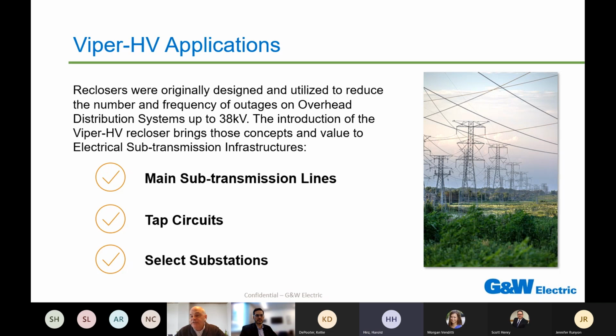On that main line is a series of taps. Those taps could be for industrial customers or interconnects, but this particular product is really conducive for those taps, where now you have complete overcurrent protection. Only that tap will be de-energized and isolated, and the rest of the infrastructure will stay on, which is a key element associated with grid resiliency and reliability.